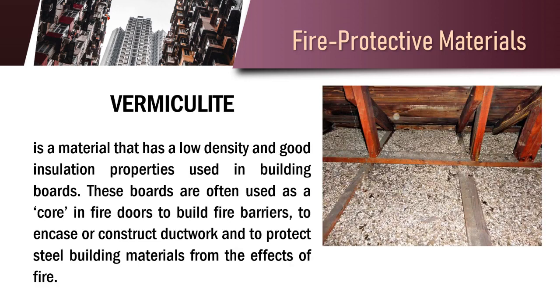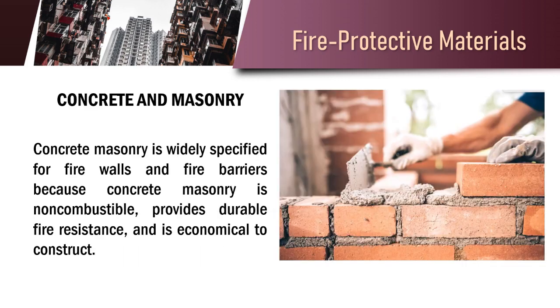Vermiculite is a material that has a low density and good insulation properties used in building boards. These boards are often used as a core in fire doors, to build fire barriers, to encase or construct ductwork, and to protect steel building materials from the effects of fire. Concrete and masonry is widely specified for fire walls and fire barriers because it is non-combustible, provides durable fire resistance, and is economical to construct.